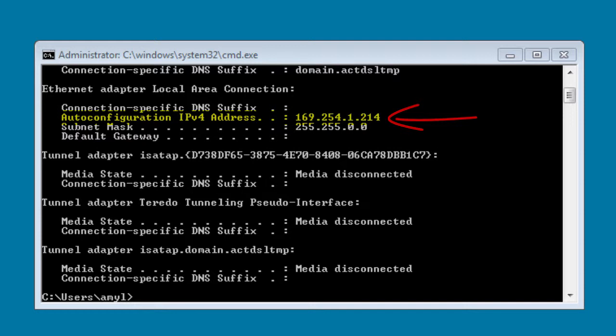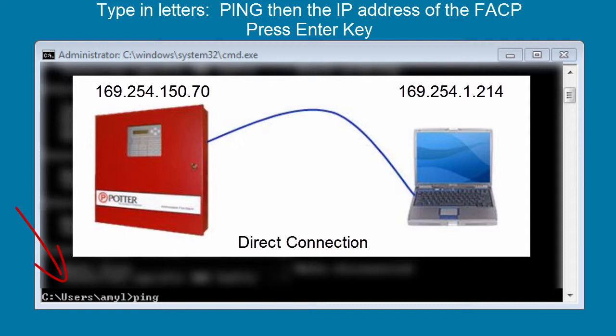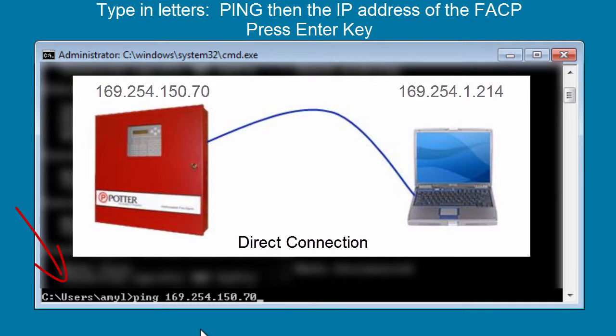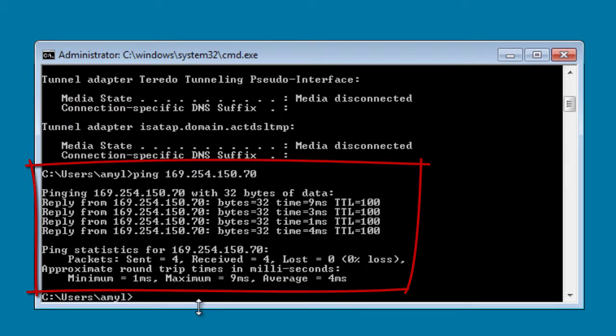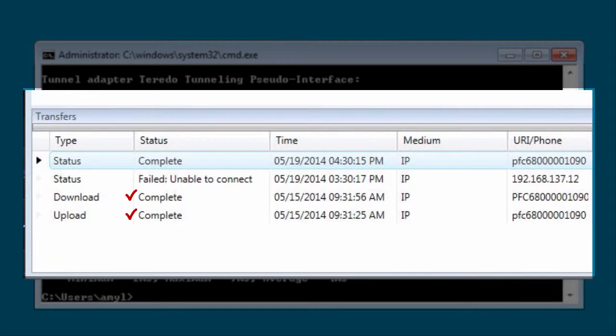This indicates that I should be able to communicate successfully with the fire alarm control panel from my laptop. Another thing you can check, if the IP addresses are similar — like we see here with my laptop and the fire panel on a private network starting with 169.254 — is to do a ping from the command prompt. I type in PING and then the IP address of the fire alarm control panel, 169.254.150.70, and hit enter. I can see that I'm getting a reply, which means I am successfully communicating with the fire alarm control panel. I can now return to my programming software and should be able to successfully upload and download programming files.